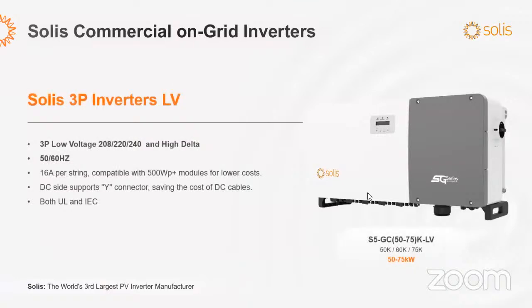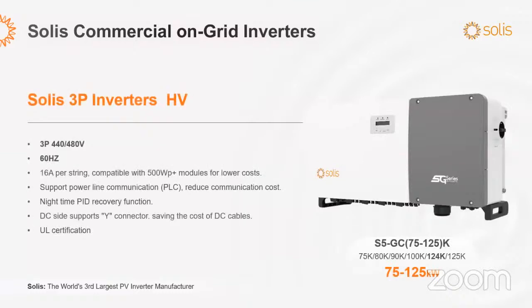So right now, this 75 kilowatt low voltage is the largest inverter we have with this configuration. So if we need higher inverters, we do have the HV line that comes in 3-phase 440, 480. However, these inverters will only come in UL certification. So in this product line, in this family, we have from 75 to 125. We also have a 124, specially designed for Mexico and Colombia because of the regulations we have here in terms of limits in GD, in distributed generation. And from there, you also have all these options.